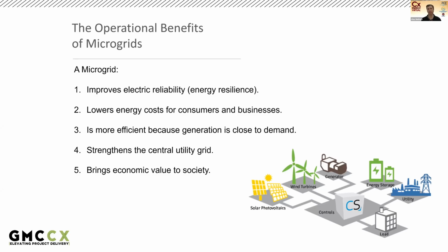In the case of a microgrid, obviously you've got that power being generated right where it's being used, and so that's one of the main reasons why it's more efficient than a typical grid. The fourth benefit is a microgrid strengthens the central utility grid because less energy is demanded from the local utility as a solar photovoltaic system operates, and less power is required as a battery energy storage system clips or curtails the power demanded during peak periods.